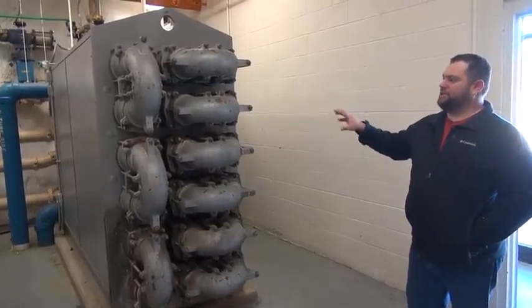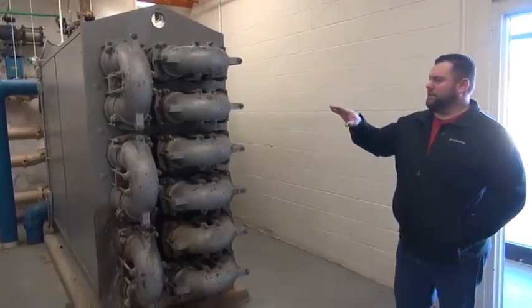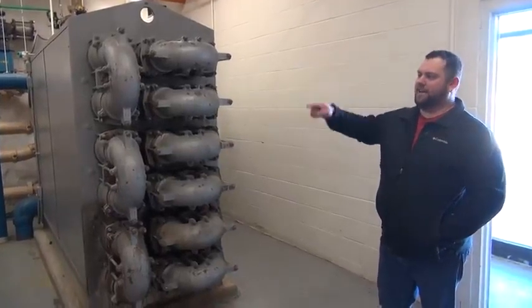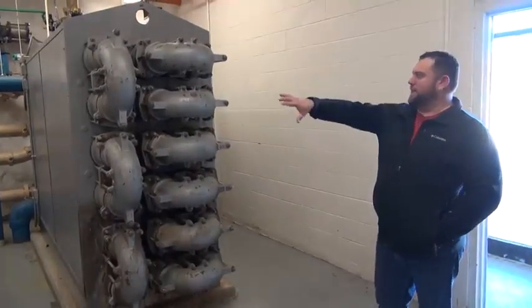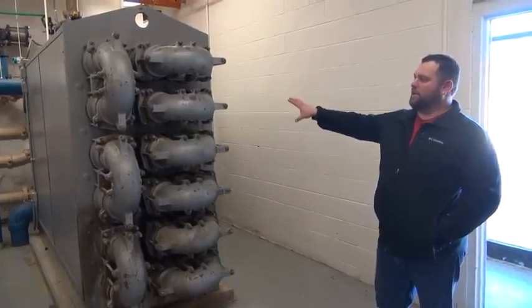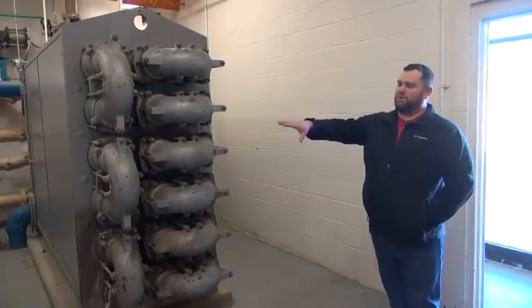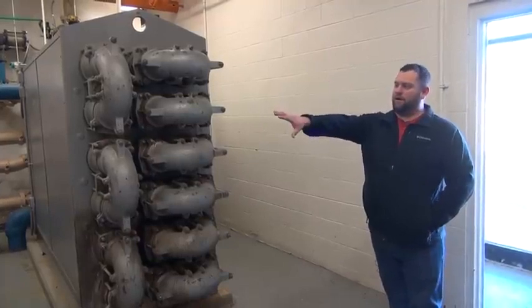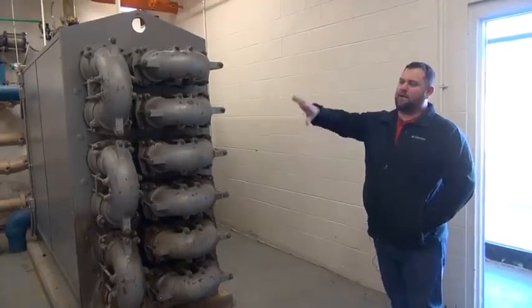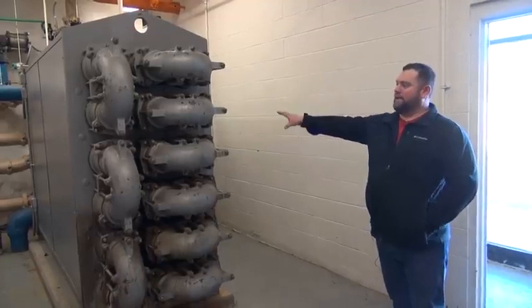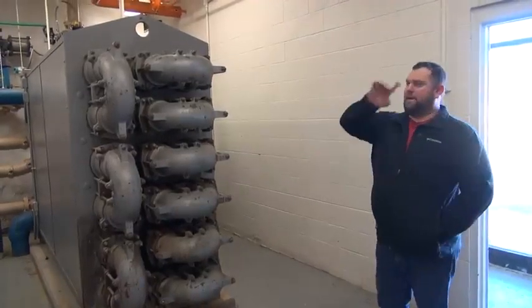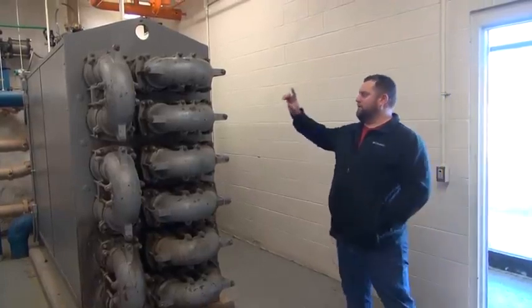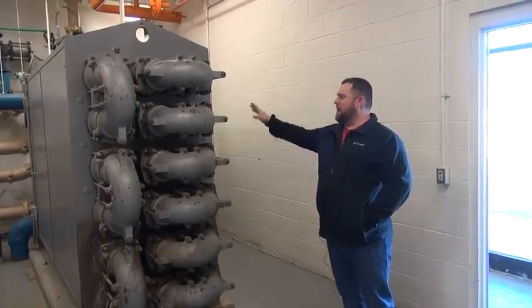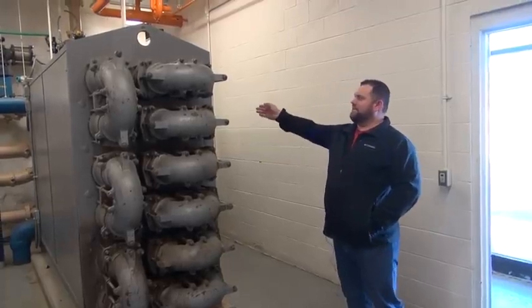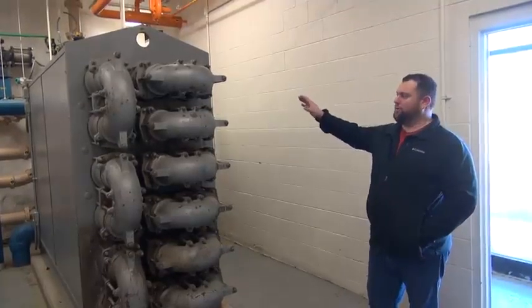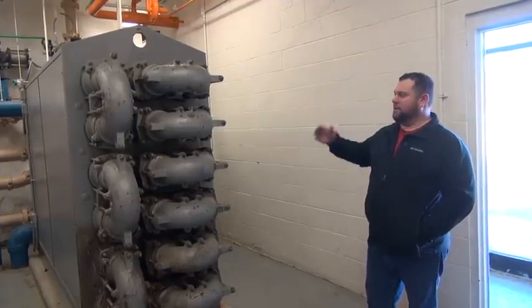The reason we prefer to use the heat exchanger is because that CHP we just looked at, the loop that goes through the block of that engine and through the exhaust of that engine is piped over to here and actually keeps this at 180 degrees all the time. So instead of having to burn a bunch of natural gas or use our methane in this boiler, we can use that CHP, which is making heat, already making power, also to heat up our digesters. So the sludge, the digesters are on either side of us right now. The sludge is pumped through these tubes, and there's that hot water jacket inside of here. It's heating that sludge up to that 131, 132 degrees, and just trying to maintain that temp at all times.